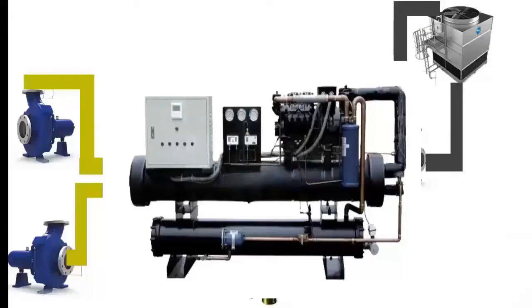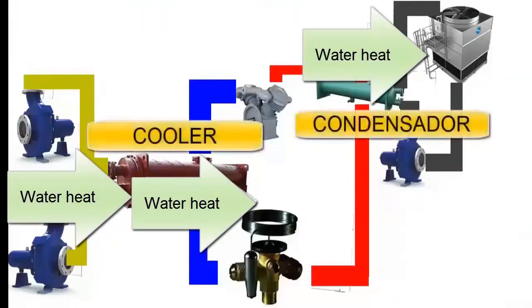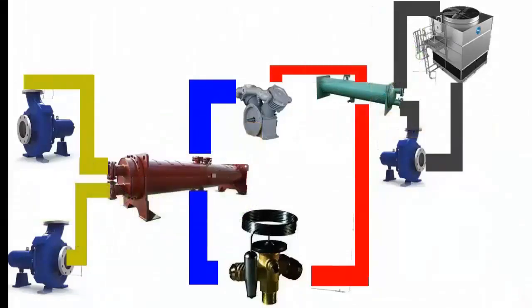From left to right, the heat from the liquid passes to the chiller evaporator — the cooler — and once it is there in the cooler, the refrigeration circuit through the refrigerant is responsible for taking that heat to the chiller condenser. That heat, as we explained in class number 1, is collected — sucked, so to speak — by the refrigerant through its evaporation.